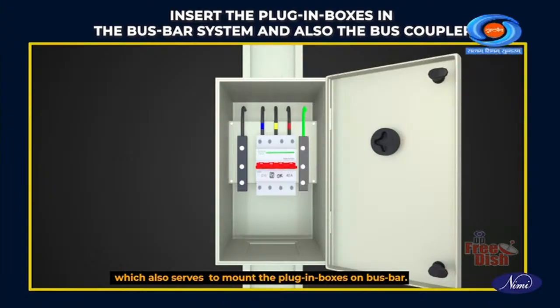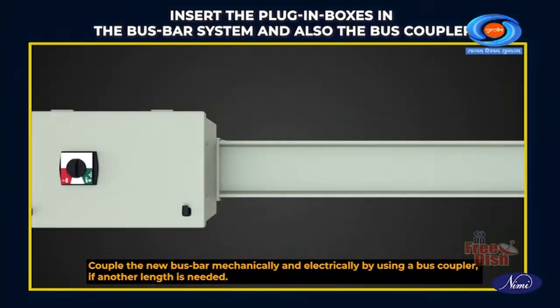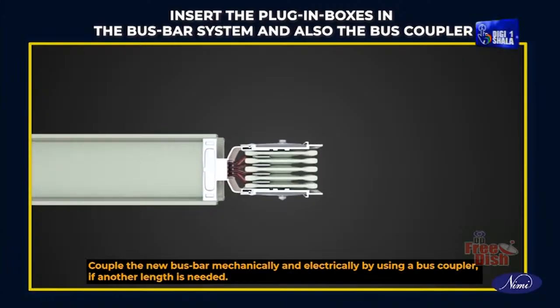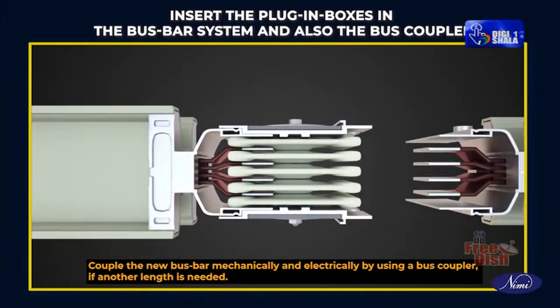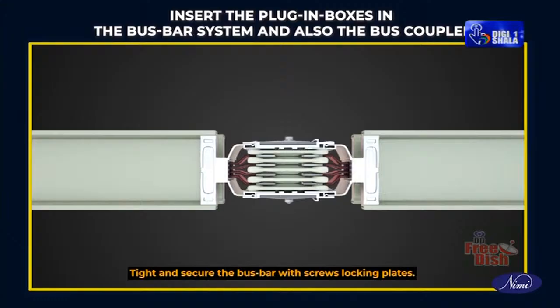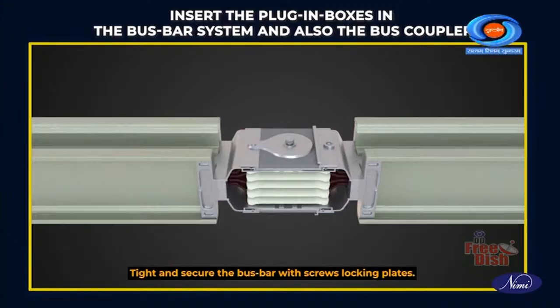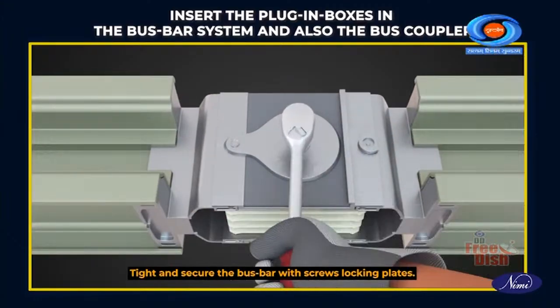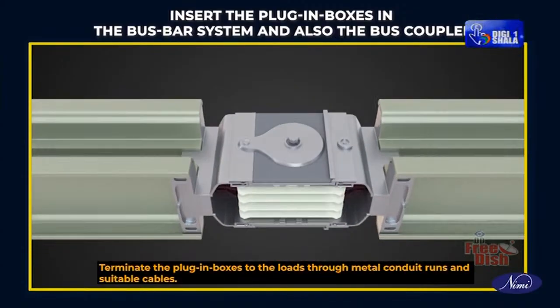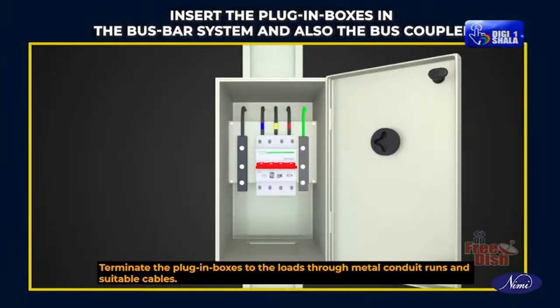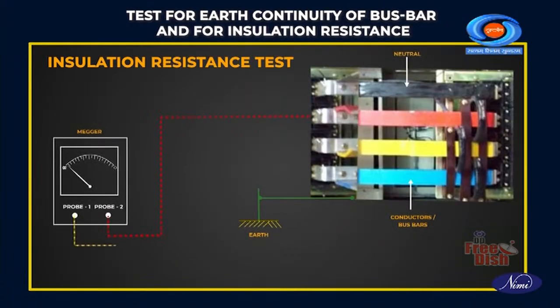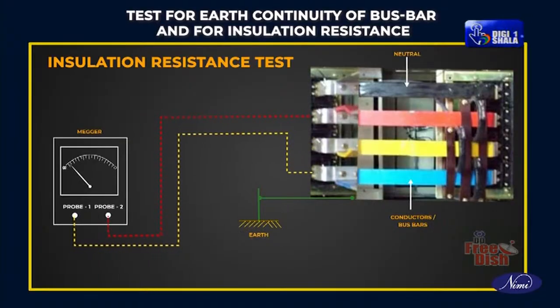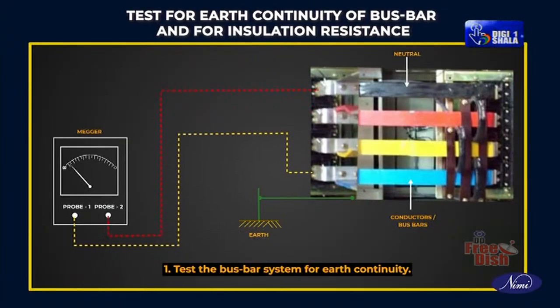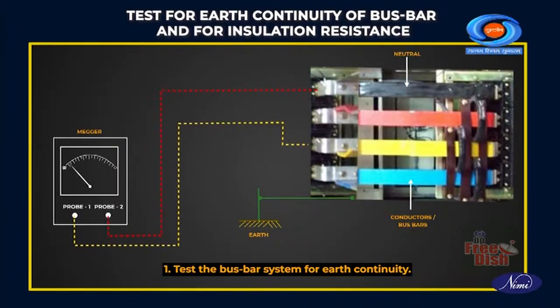on the bus bar. Couple the new bus bar mechanically and electrically by using a bus coupler if another length is needed. Tighten and secure the bus bar with screws and locking plates. Terminate the plug-in boxes to the loads through metal conduit runs and suitable cables. Test for earth continuity of the bus bar and for insulation resistance. Test the bus bar system for earth continuity.